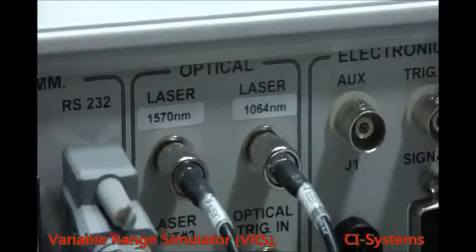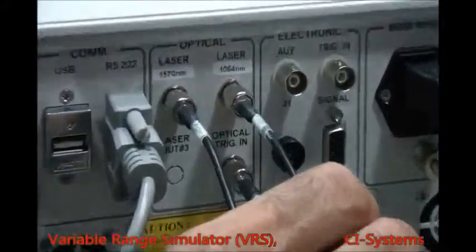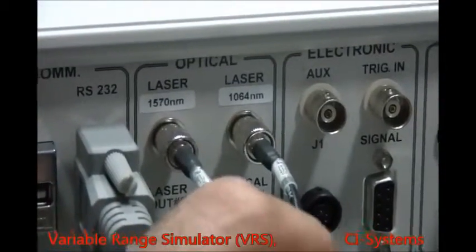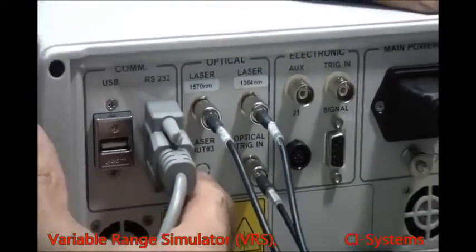On the output, since this is a dual wavelength VRS, you have two fiber optic outputs. One is a 1.06 wavelength laser output and one is a 1.57 in this case. As I said before that we can have up to three, so here we can see that this is the third output.